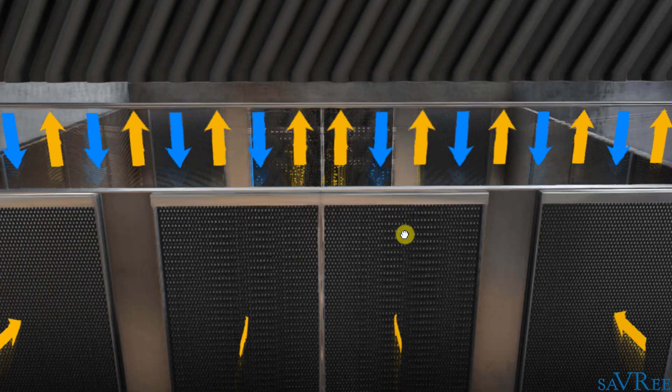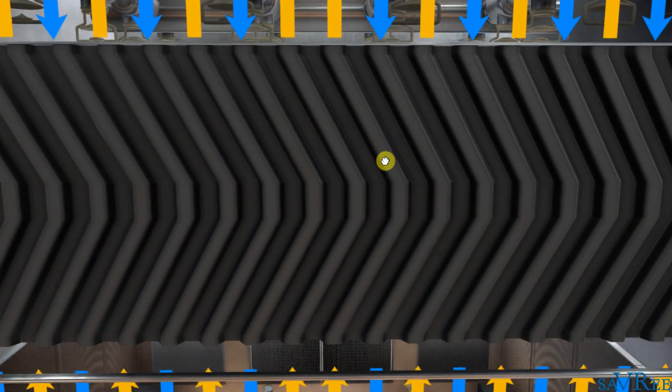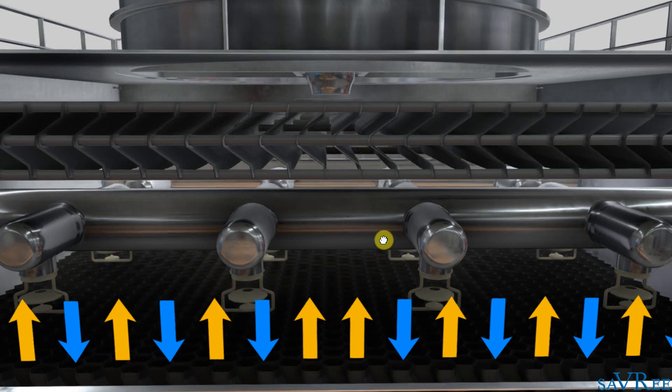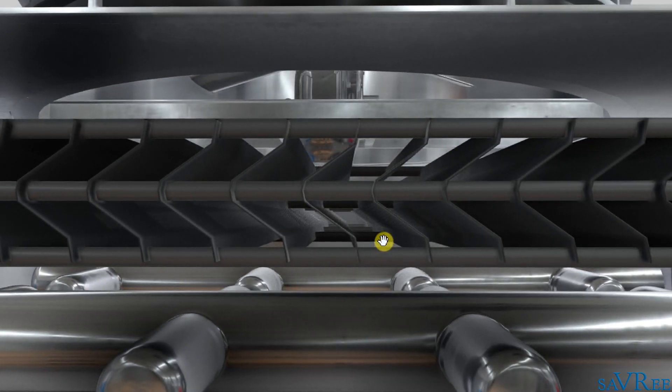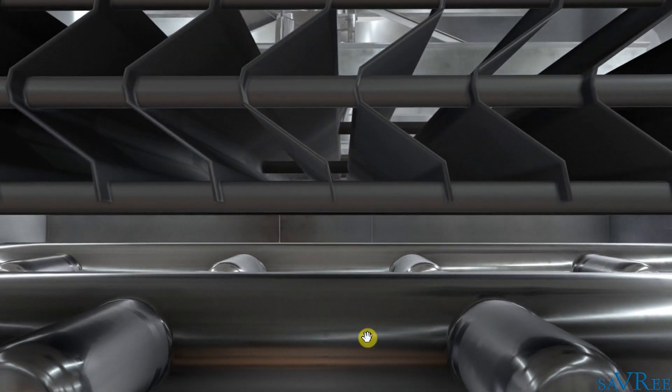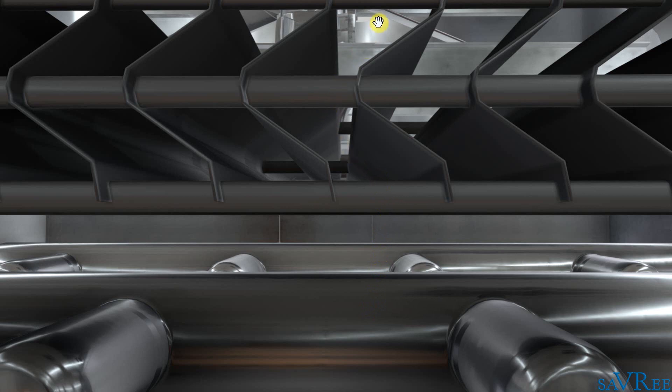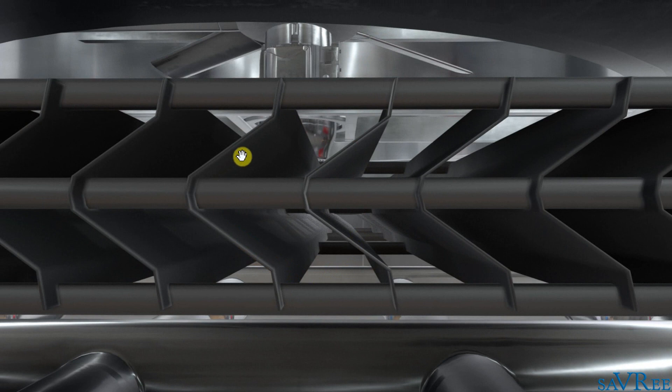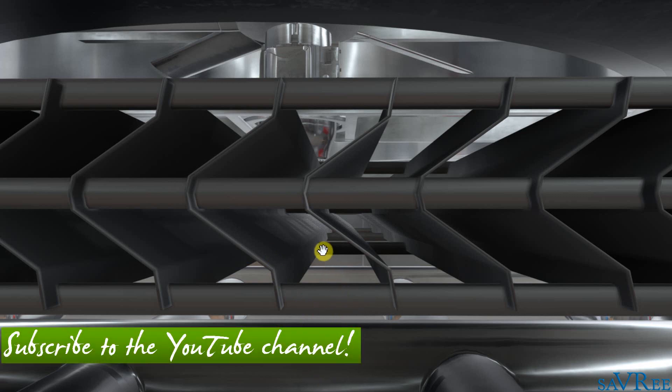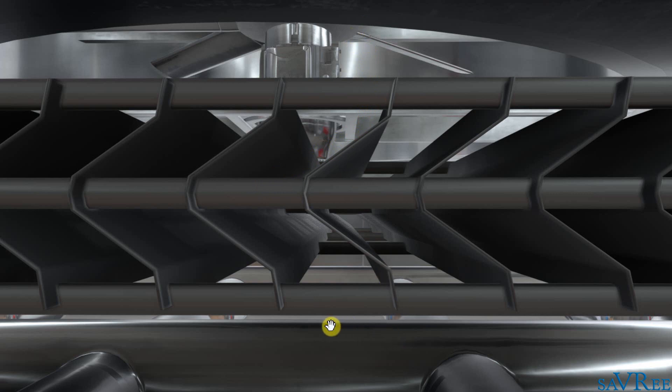Now what happens to the water that evaporated? Well we don't want it to just drift away because if it drifts away, then we have a water loss. And this means that we're actually going to have a financial loss as well. So rather than have it drift away, what we're going to try and do is recapture some of that evaporated water. So we've got the water vapor coming up and then it's going to try and pass through this drift eliminator. You can see it's got this very weird V type shape, looks like a V that's been spun 90 degrees. And what this V is actually doing is forcing the water vapor to pass through at an angle. So it's got to flow through here rather than just flowing straight up and out. It's got to change direction, change direction again, and then change direction again to flow up and out.